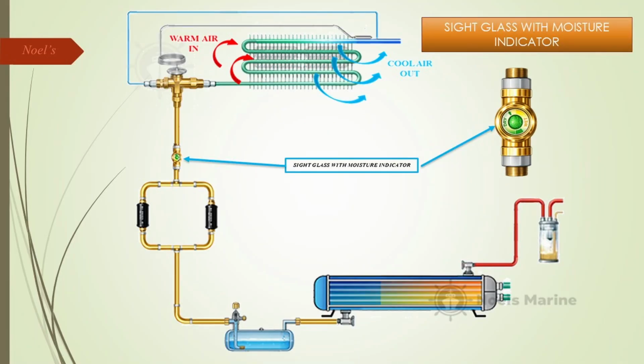And right after that, there is a very simple but critical diagnostic tool, the sight glass. It's literally a little glass window built into the pipe. And engineers are looking through this for what exactly? They're checking for bubbles. If you see bubbles, it usually indicates low refrigerant or poor subcooling. You're also checking a tiny indicator inside for moisture. If moisture gets in, it can create acid and ruin the system.